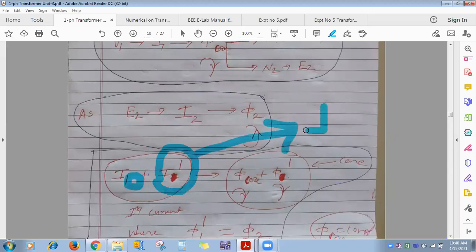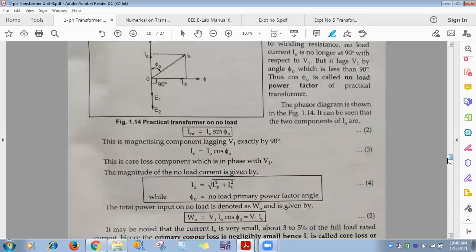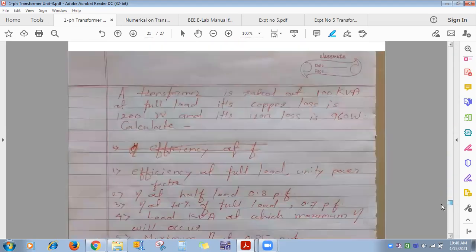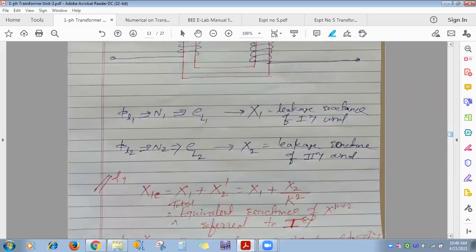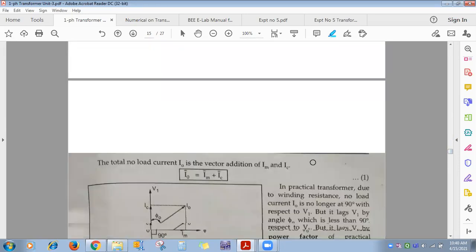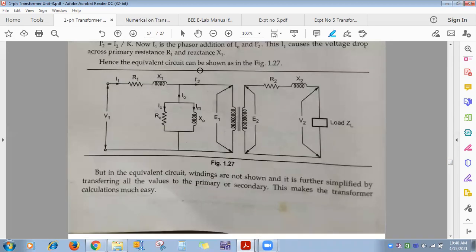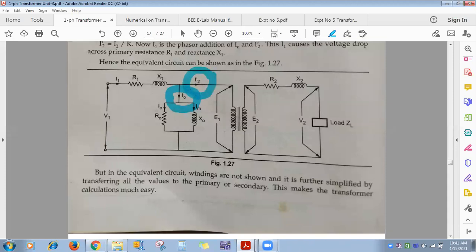When the secondary is open: only I0 (no-load current) flows. When load is connected: total primary current = I0 + I2-dash. I2-dash is the additional current the transformer draws to counteract the flux produced by I2 and maintain constant core flux.